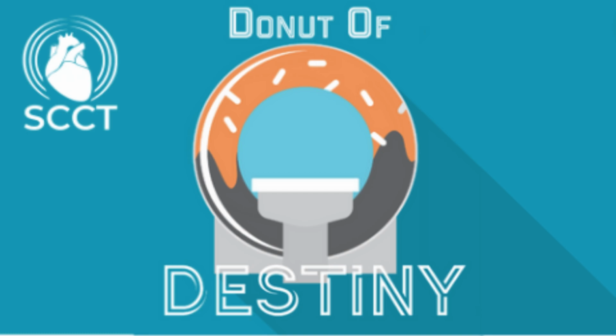If it's below a certain energy level, say 30 keV, it would be just absorbed by the body as dose. We often see signals on the detector, whether it's photon counting or energy integrating, at that level. But in an energy integrating system, that's lumped together with all of the noise and all of the signal from the helpful X-rays. With photon counting, since we are measuring the energy of each one, if we have a signal that represents one of those impossible X-rays, we just throw it away. We say, that's not true. And so it allows us to get a much better signal quality by eliminating all of that electronic noise. And so again, it's not one advantage of photon counting. It's many different things that all come together that really allow us to push these clinical fields forward.